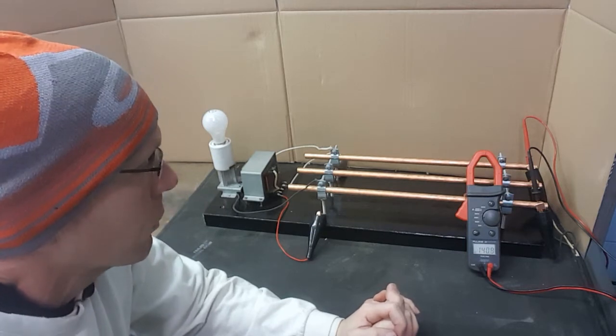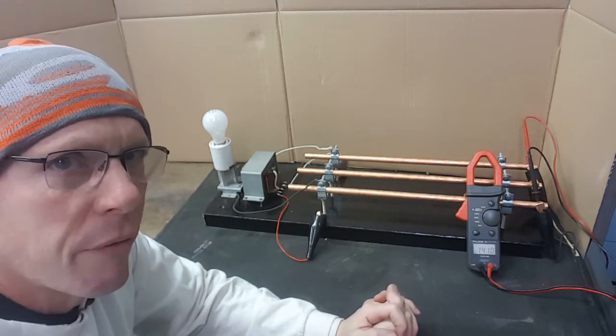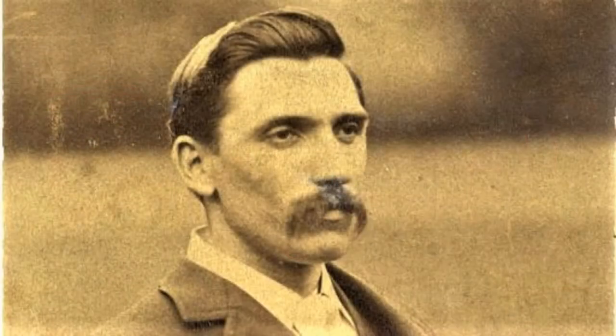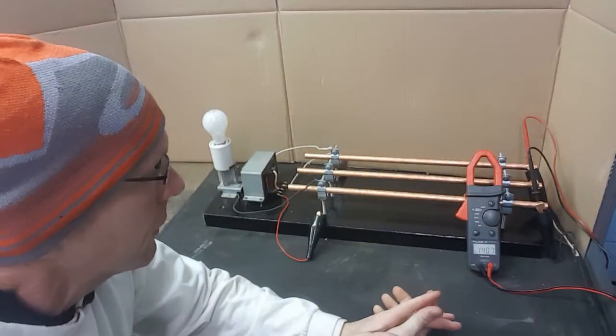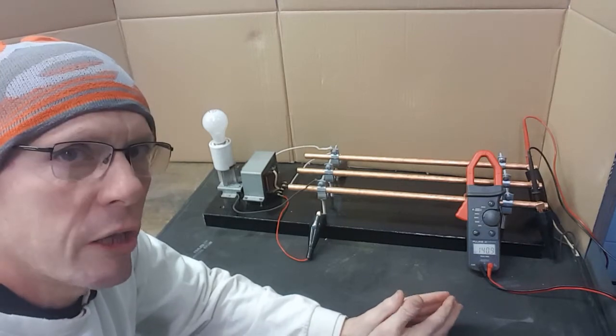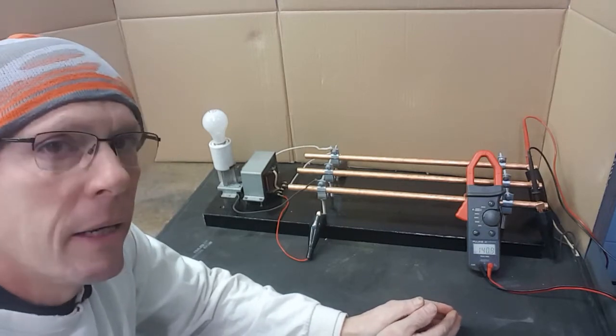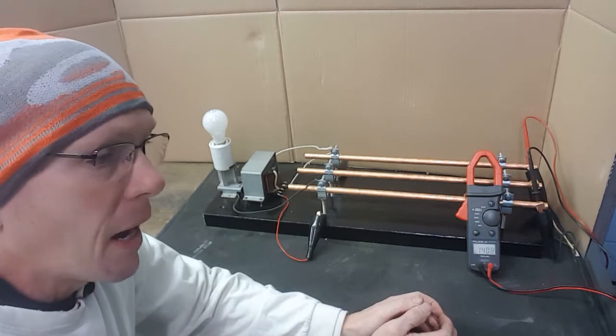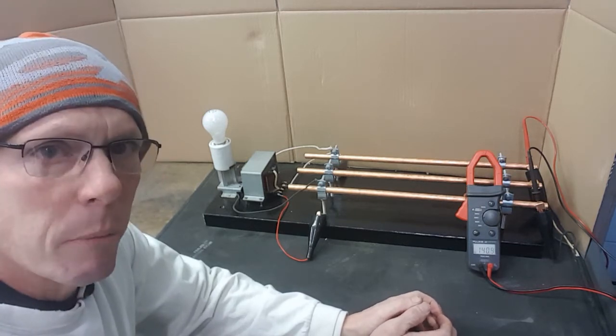In this article they were talking about something known as the Ferranti effect, which was apparently named after the guy who discovered it. The Ferranti effect is a condition where the voltage at the end of a transmission line can exceed the voltage at the beginning of the transmission line by 15 to 20 percent in some cases.